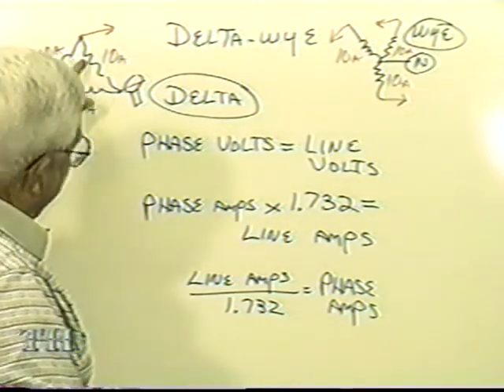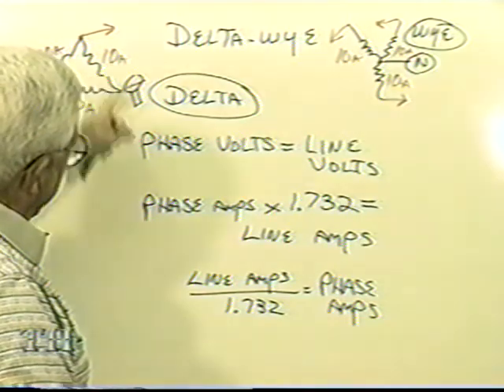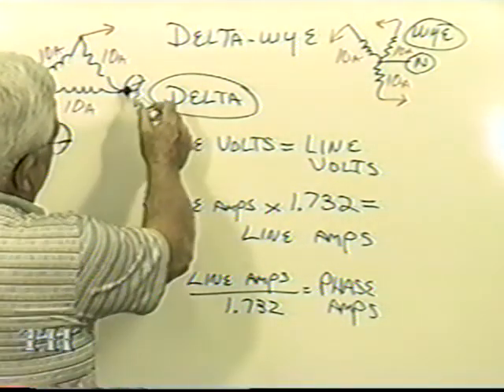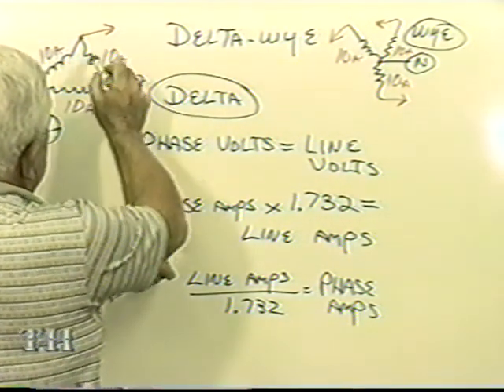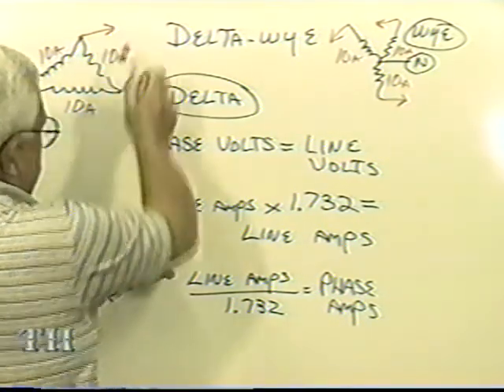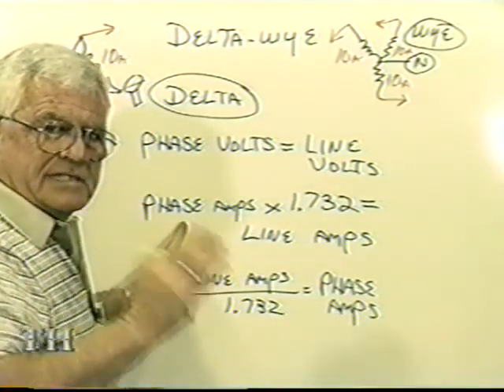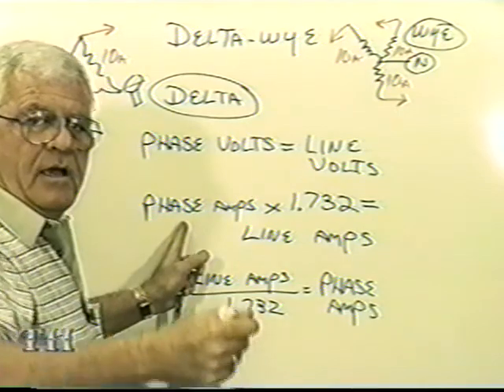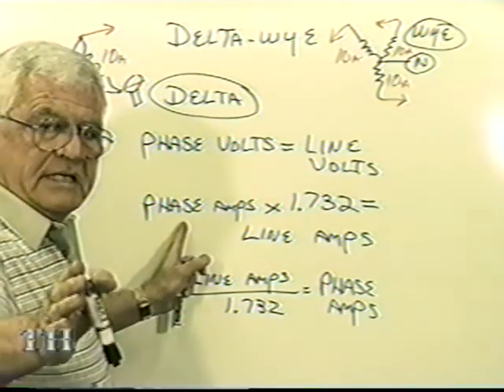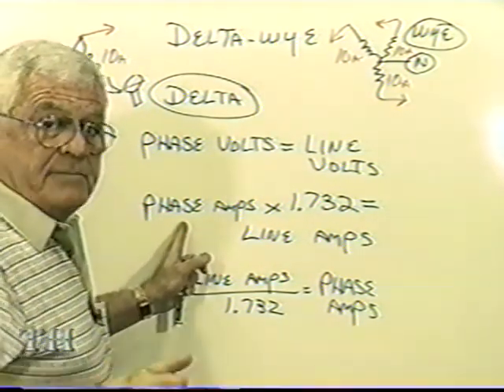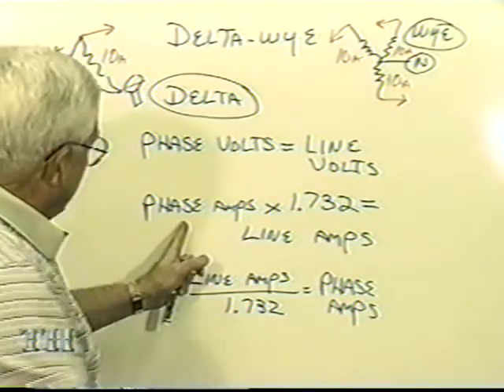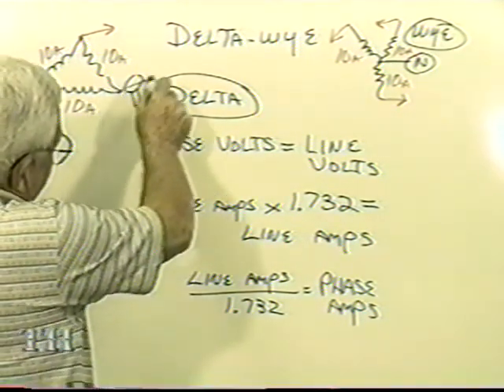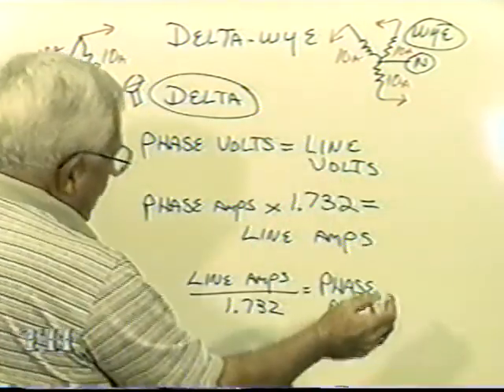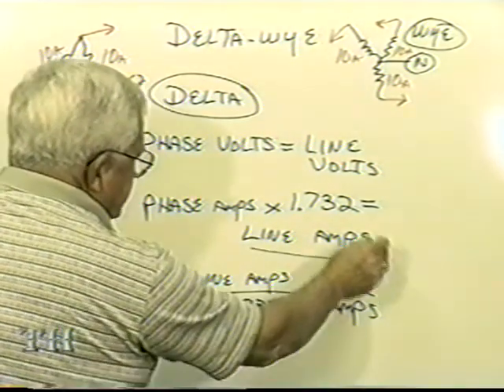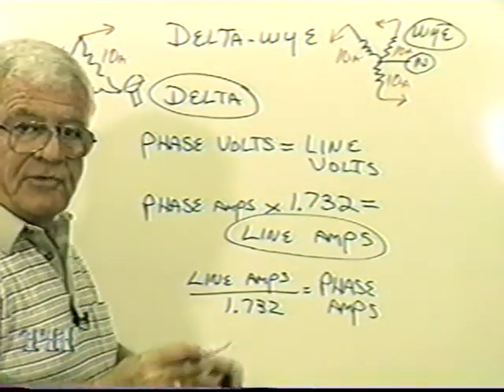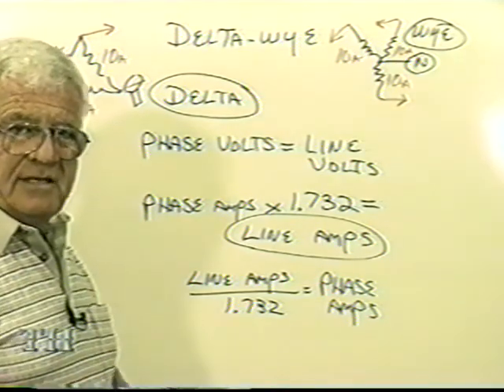You would take the phase amps. See, that 10 is a phase amp, and I want to know lines. See, these are lines. This is coil, phase, line. That's the first thing you have to distinguish. What is a phase? What is a line when you see it in a sketch or in a typed question? When I put my amp clamp on the line, I want to know line amps. That's what they're asking me. What's the line amps, not the phase amps?